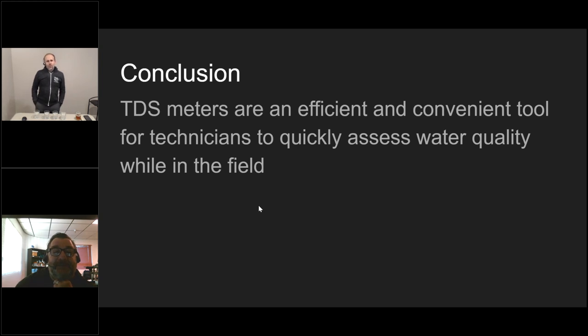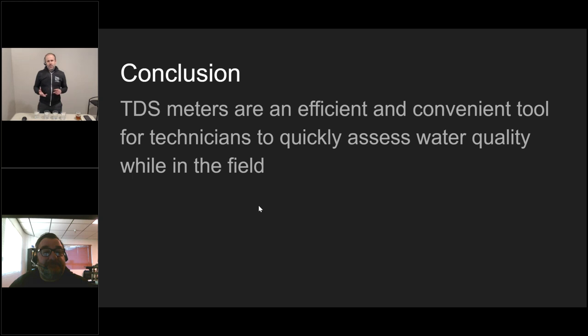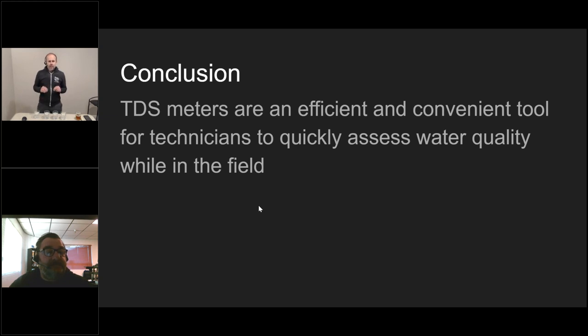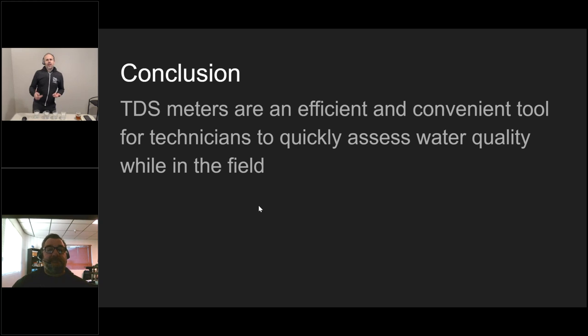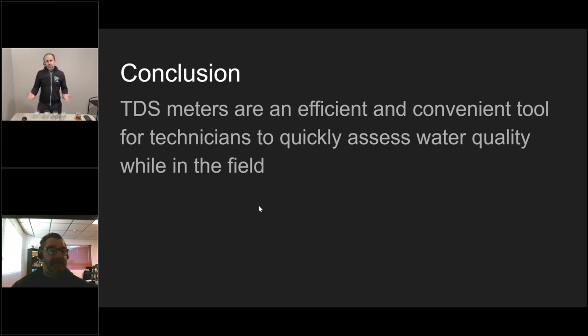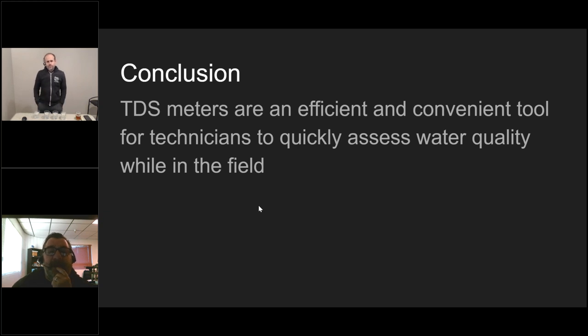Please explain more about 442. 442 is a calibration solution that was created by a company called Myron L, and they make TDS meters and water quality testing equipment. 442 is a calibration solution that you use with your TDS meter to determine whether to set the TDS meter up so that it will read properly to a relative degree. It's designed to approximate the concentration of ions in most fresh waters as a calibration solution, as opposed to salinity meters, which if you have a meter that says calibrate to NaCl, then that's a salinity meter and the factorization is set and you're just calibrating it with that salt solution.